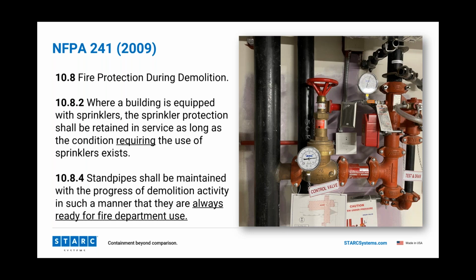So when your building has standpipes, make sure that they are always ready for department use. And then, of course, like I said, the sprinkler system has to remain in service. This is even during demolition. We're talking about demolition now. Even during the demolition side, your sprinkler system has to remain in service as long as there's a condition requiring it. That condition is the 1 hour barrier, the one hour fire barrier. It has to be an active sprinkler system.